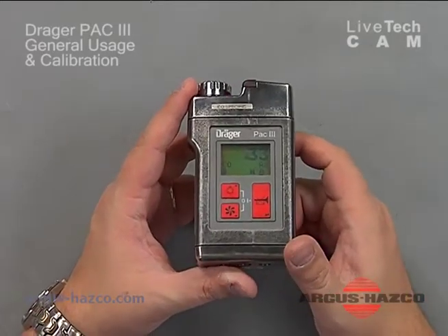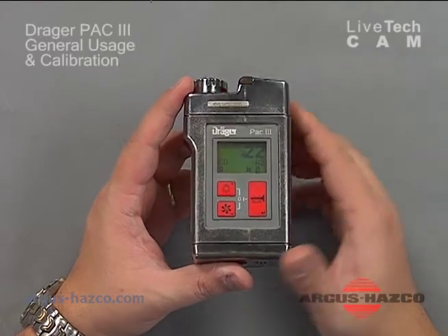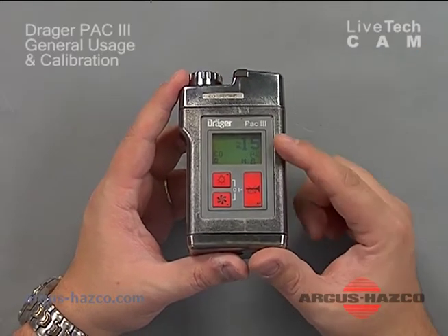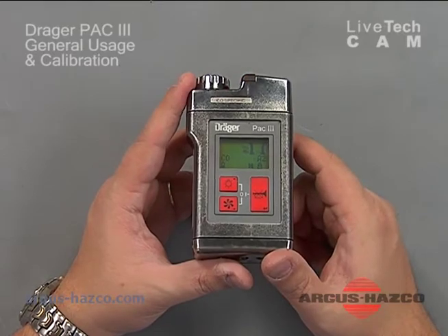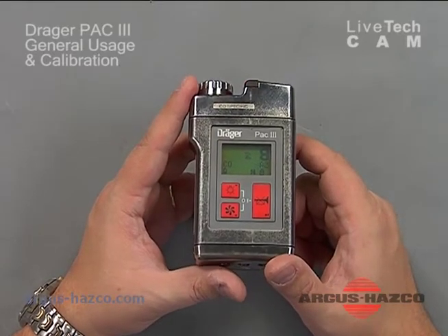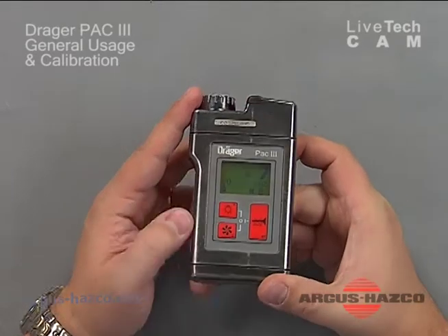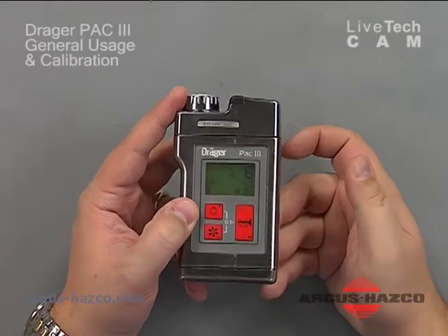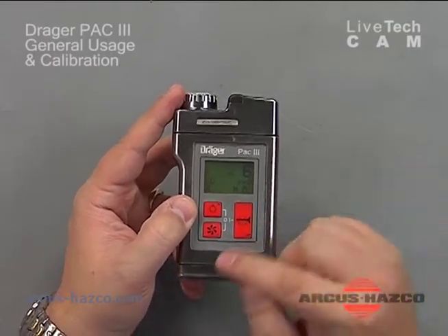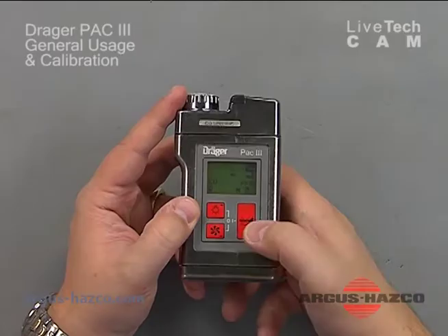It's above the 25 or 35 parts per million, however your alarm is set. And even when it drops below, it's what's called a latching alarm. It'll stay in alarm until you acknowledge, yes, I know you've been in alarm. That's by hitting your enter button again here. That's what that horn with the X through it means. You're acknowledging your alarm condition. So now it's going back down to 0. Your unit is calibrated. The I for the warning is now gone, and the unit is ready for use.